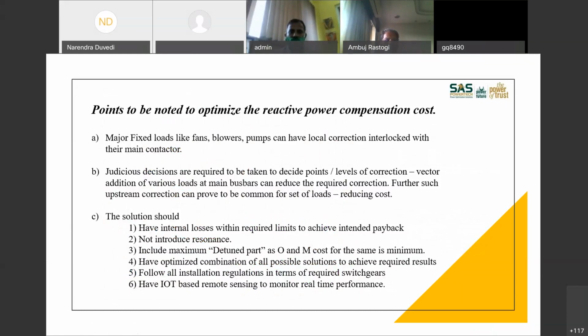In such cases, you can interlock a local fixed correction with a local contactor with that motor and correct the power factor there itself. The basic advantage is your automatic system costs can go down. So you can choose this wherever you have it in your plants. Maybe you can select only larger loads because smaller loads may not affect your metering power factor to a larger extent, but this is possible. Judicious decisions are required to decide points and levels of correction, vector addition of various loads at main bus bars.